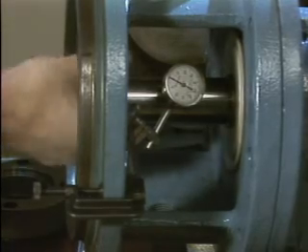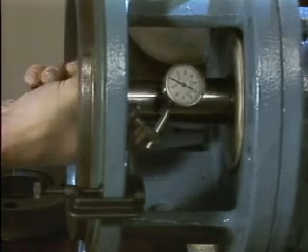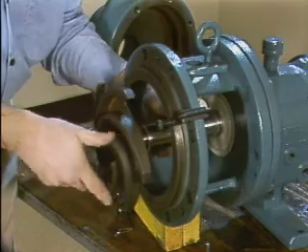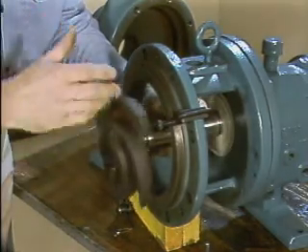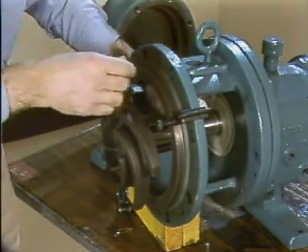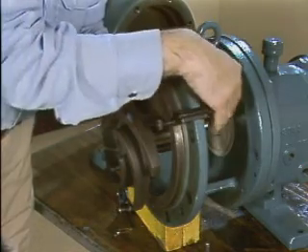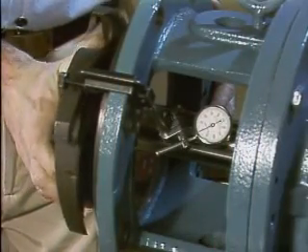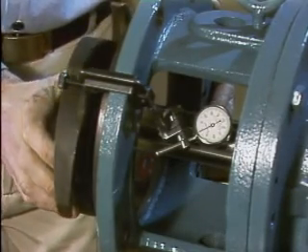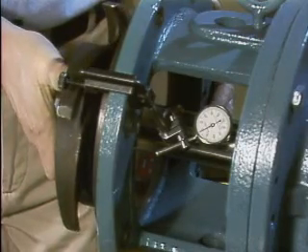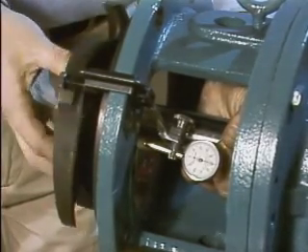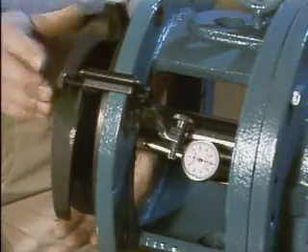To determine if the runout is excessive, you'll need to refer to your company's policies and procedures or to the pump manufacturer's specifications. Next, sleeve runout is checked. Basically, this is done by installing the shaft sleeve in the impeller, which holds the sleeve in place, then repeating the process that's used for measuring shaft runout with a dial indicator. Checking sleeve runout is important because the seal's rotating element is mounted on the sleeve. Excessive sleeve runout could prevent the rotating element from being properly positioned next to the mating ring. Once the sleeve runout check is complete, the impeller and the sleeve are removed from the shaft again so that other checks can be made.